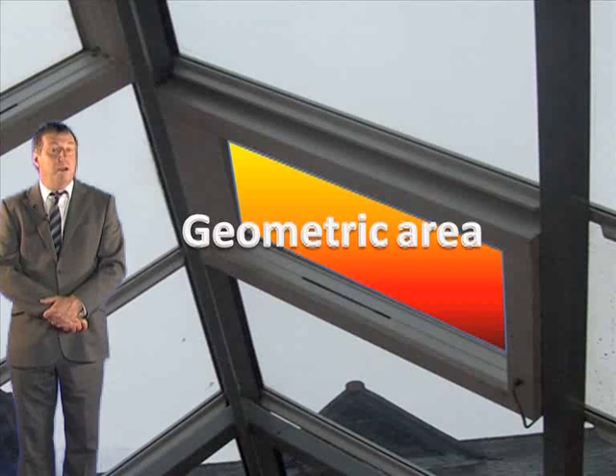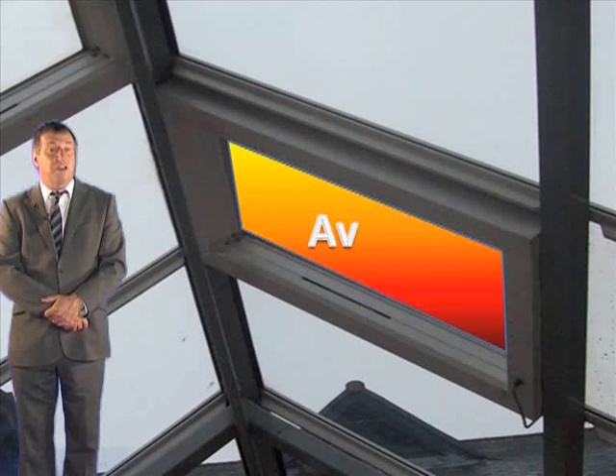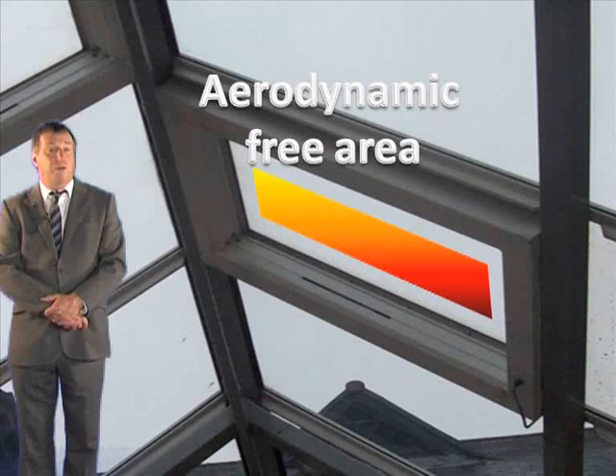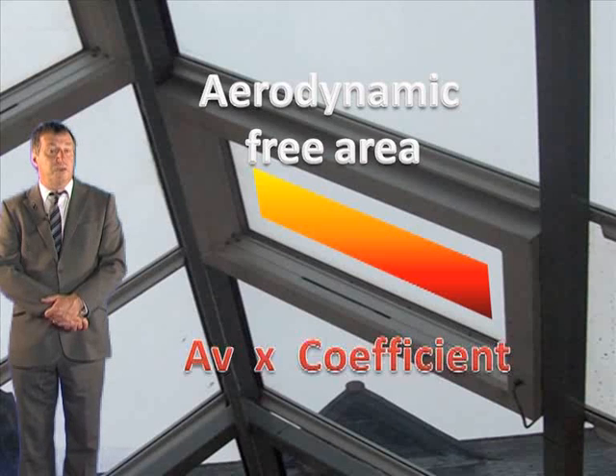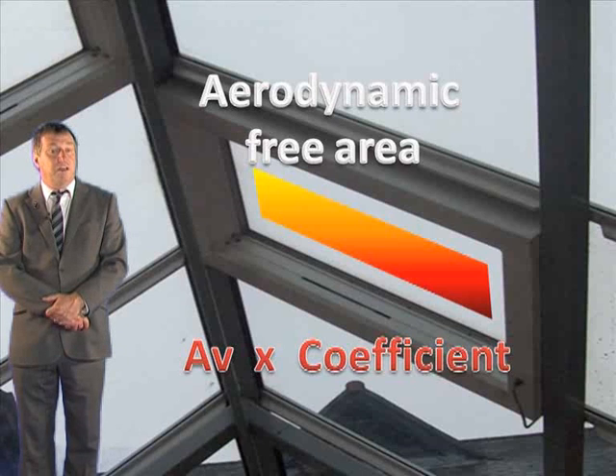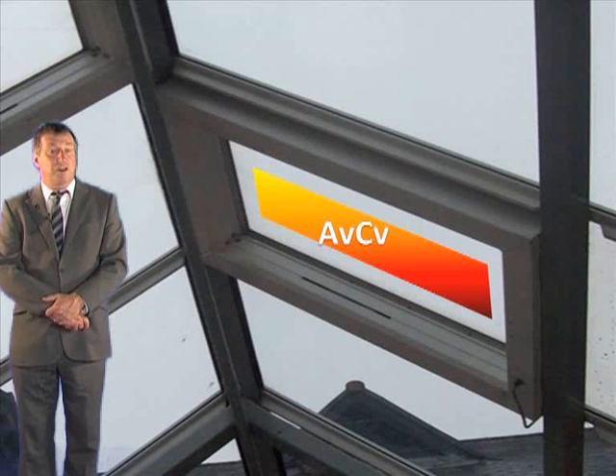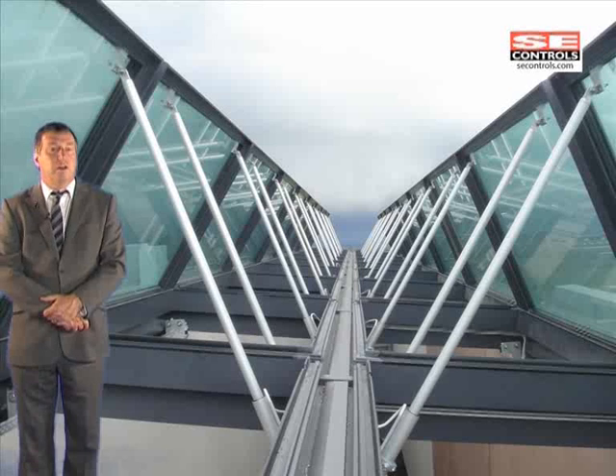The geometric or measured area of the ventilator is designated as AV, and the aerodynamic free area is found by multiplying the geometric area by the coefficient of ventilation, and it is designated as AVCV, which represents the product of the two terms. So why do we generally calculate AVCV and not AV when we work out the required area of ventilation for a reservoir?